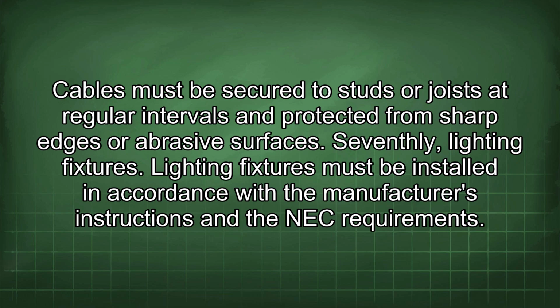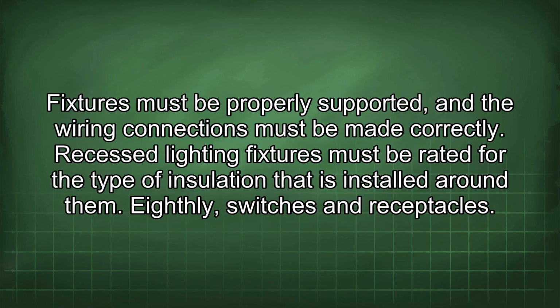Seventhly, lighting fixtures. Lighting fixtures must be installed in accordance with the manufacturer's instructions and the NEC requirements. Fixtures must be properly supported, and the wiring connections must be made correctly. Recessed lighting fixtures must be rated for the type of insulation that is installed around them.